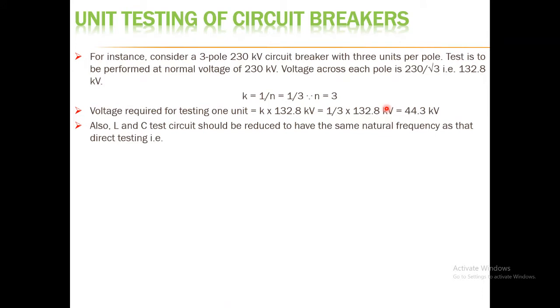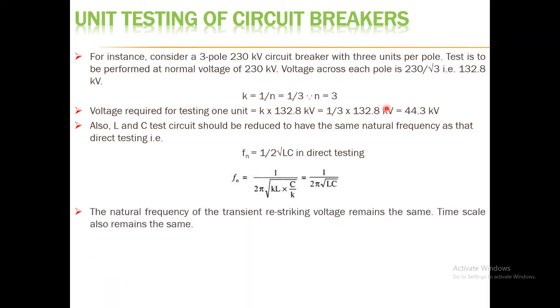Also, the L and C of the test circuit should be reduced to have the same natural frequency as that of direct testing. In direct testing, FN = 1 / (2π √(LC)). In unit testing with scaling, FN = 1 / (2π √(KL × C/K)) = 1 / (2π √(LC)). So the natural frequency of the transient restriking voltage remains the same, and the time scale also remains the same, as confirmed by this equation.